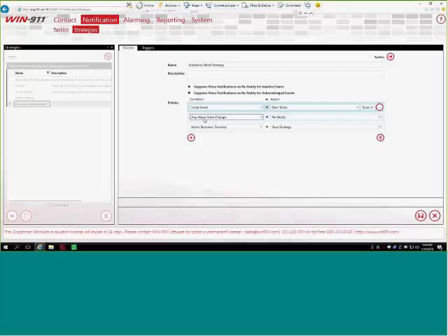And if I have an alarm state change, what do I want to do? Well, I want to re-notify anyone that had been notified previously about the alarm so they get the update, so they have the most current information. And if the alarm becomes terminal or is normalized, which means the alarm is inactive and acknowledged, then I'll stop the strategy. If I wanted to stop the strategy on acknowledgement, which means I'll stop notification when the alarm gets acknowledged, I just have to choose that drop down.